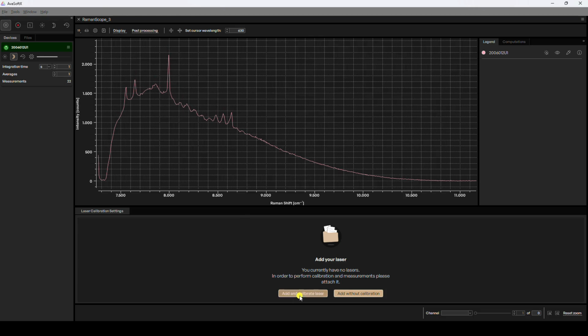For higher accuracy, click Add and Calibrate Laser and calibrate using a sample with well-defined peaks, such as PTFE or paracetamol, or a known laser wavelength. In this example, we demonstrate calibration using PTFE. Fill in the expected laser wavelength. Click Start Calibration. When the new measured wavelength doesn't change, click Stop Calibration. Click Save. Now the window shows corrected Raman shift spectra.